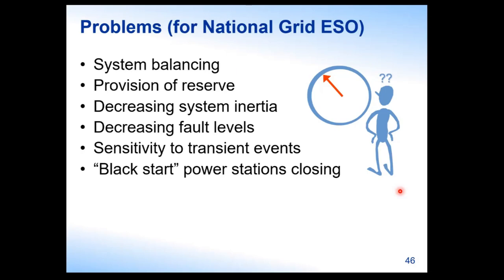If you connect a generator to a transmission line with nothing else connected to it, that unfortunately looks like a big capacitor, and generators aren't very happy being connected to large capacitors. So there are some technical requirements for a power station that's going to provide black start, and that was provided by all these coal-fired power stations, which have now shut down. So I'm not sure how National Grid is able to provide black start.